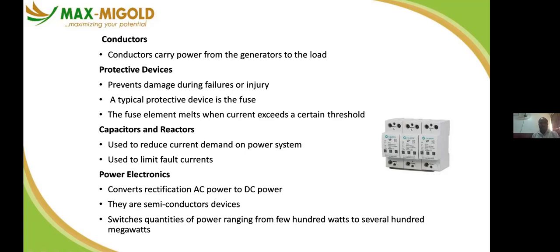We have the capacitor and the reactors. They are also used as power limiters. So they are used to regulate the value of supply that is coming into your appliances. They are used to reduce current demand on the power system, and to limit fault current. So these are capacitor and reactor.